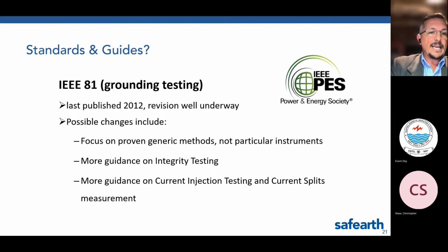So in IEEE 81, which was originally just on soil resistivity testing, but it's now on all kinds of grounding testing, there's changes in there that I expect will talk about proven methods, won't talk about instruments. There's a very important line to be drawn where we talk about methods, but we don't talk about any particular brands or styles. There will be more guidance than there's been before on integrity testing, and there's a lot more guidance on current injection testing and the measurement of current splits.